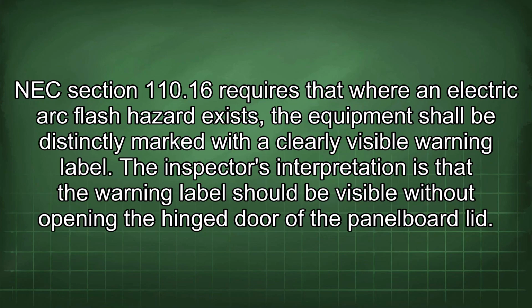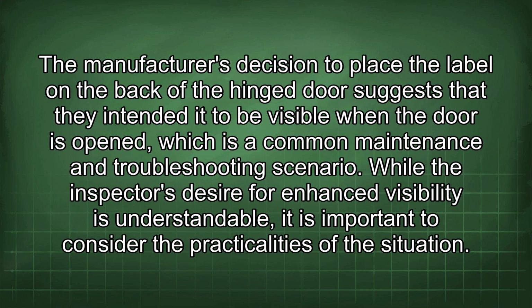NEC Section 110.16 requires that where an electric arc flash hazard exists, the equipment shall be distinctly marked with a clearly visible warning label. The inspector's interpretation is that the warning label should be visible without opening the hinge door of the panel board lid. The manufacturer's decision to place the label on the back of the hinge door suggests that they intended it to be visible when the door is opened, which is a common maintenance and troubleshooting scenario.